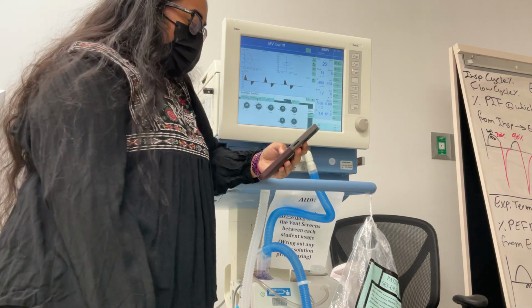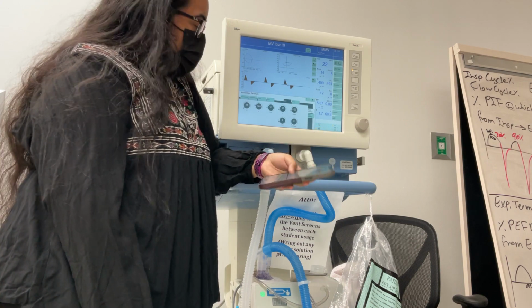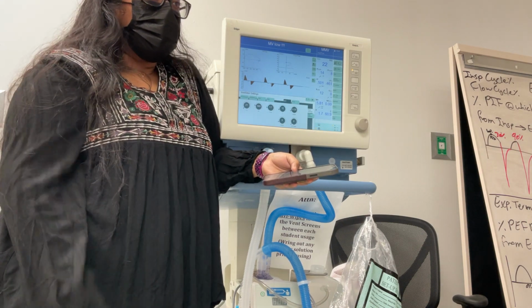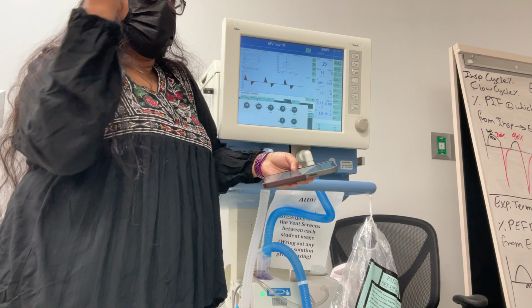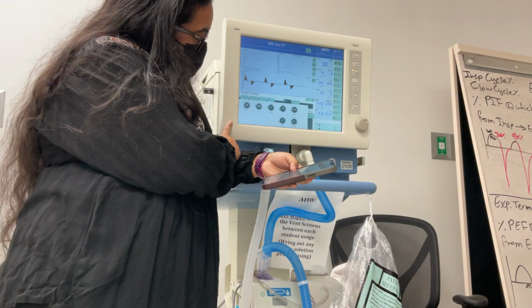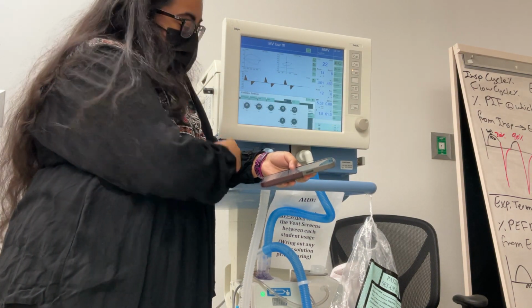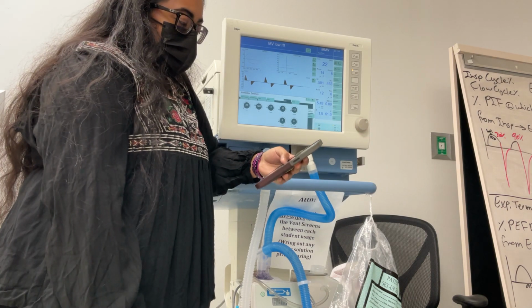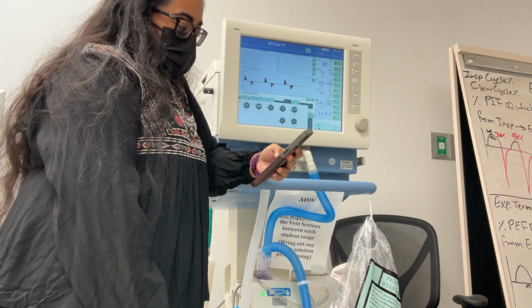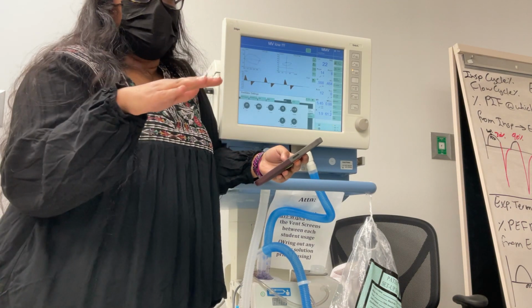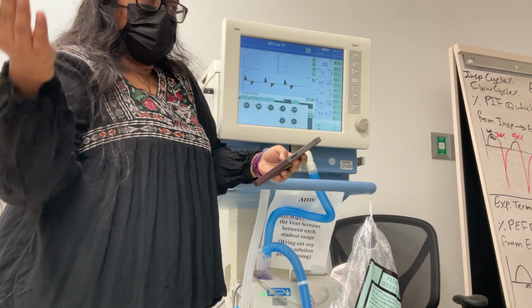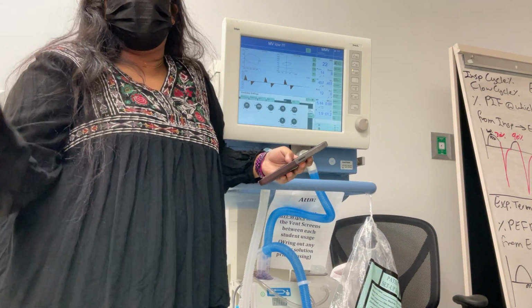Yeah. So mandatory minute ventilation only gives you mandatory breaths if your spontaneous breath rate and volumes are less than what you have set with your rate and your volume here. If you're breathing over it, it's not gonna do anything, you just do your own breaths. If you're under your calculated minute ventilation, then it'll deliver additional machine breaths to get you back to that target minute ventilation that you want.